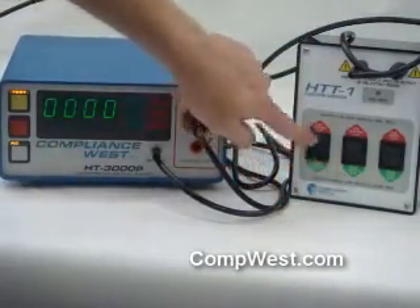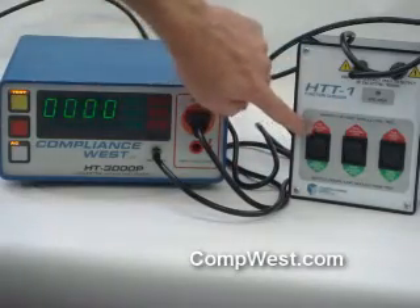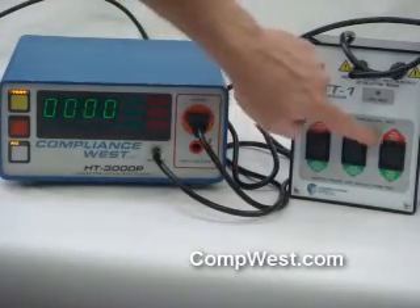The switches are either green for pass or red for fail. You can either do the ground test, a leakage test, or a Hipot failure test.